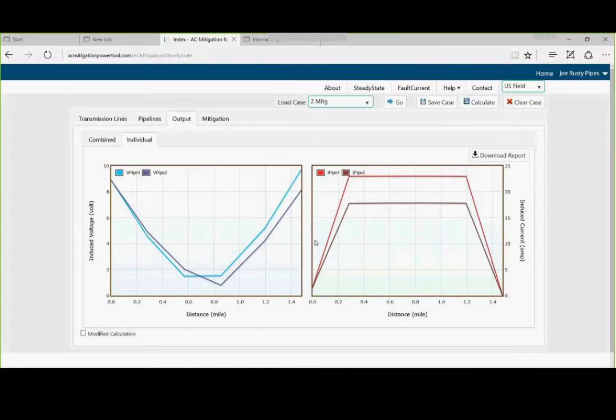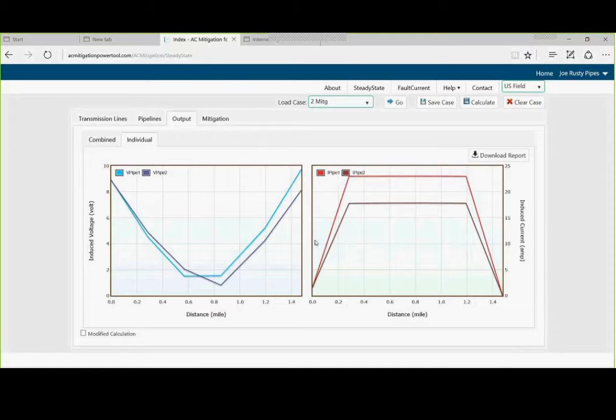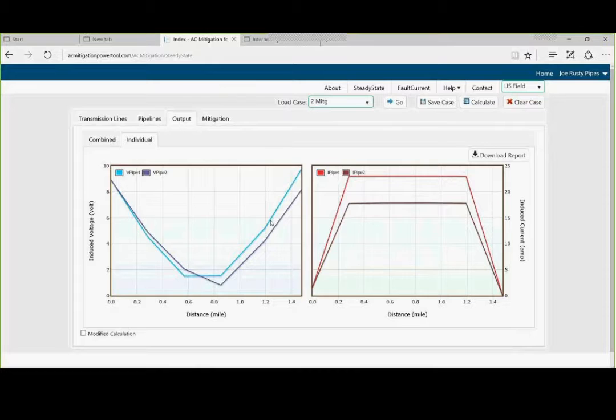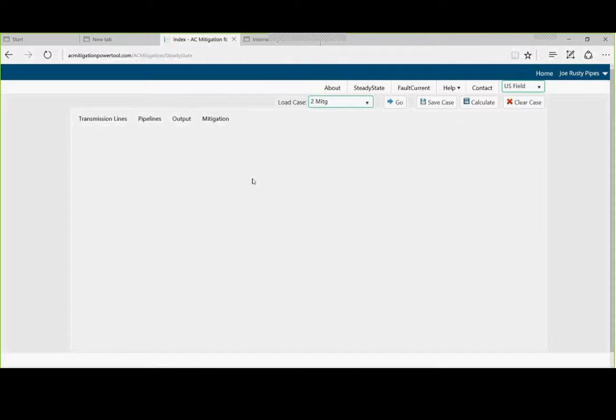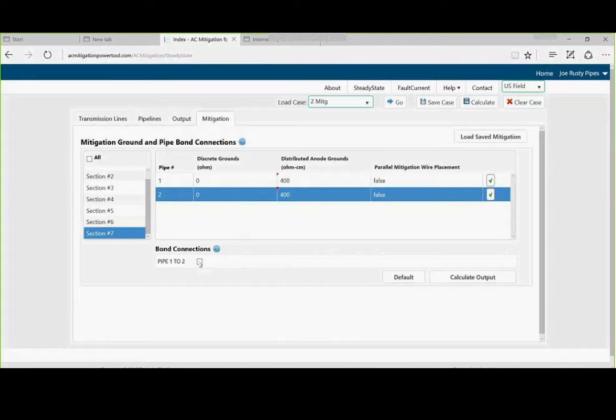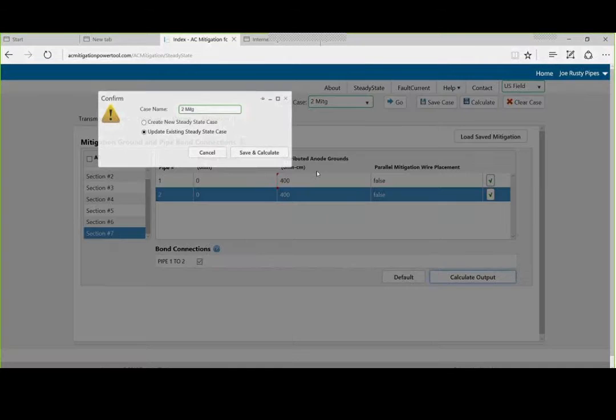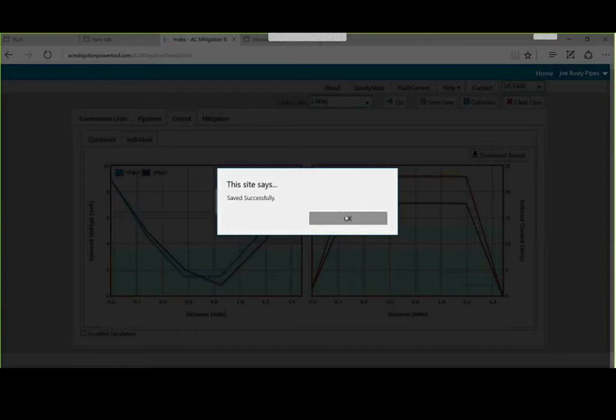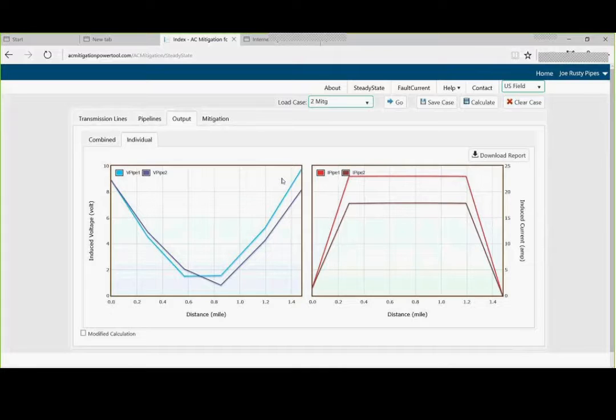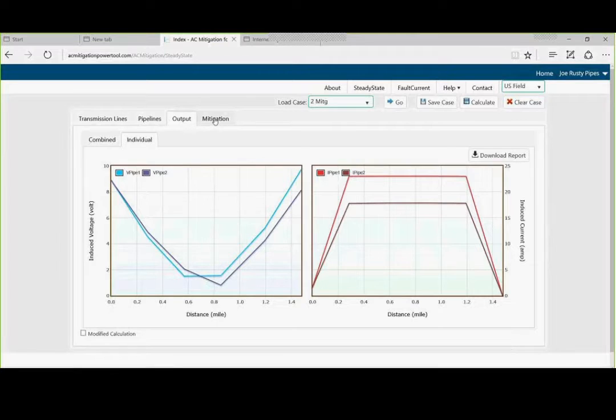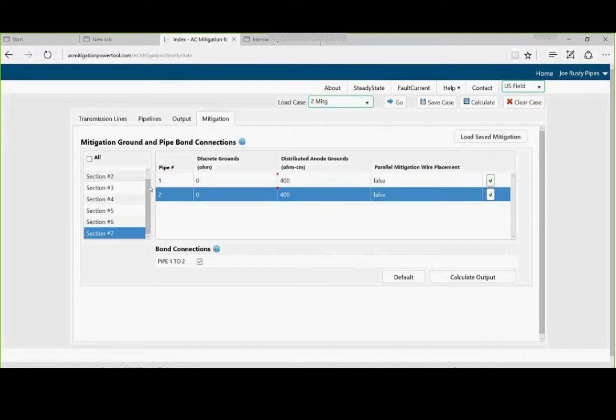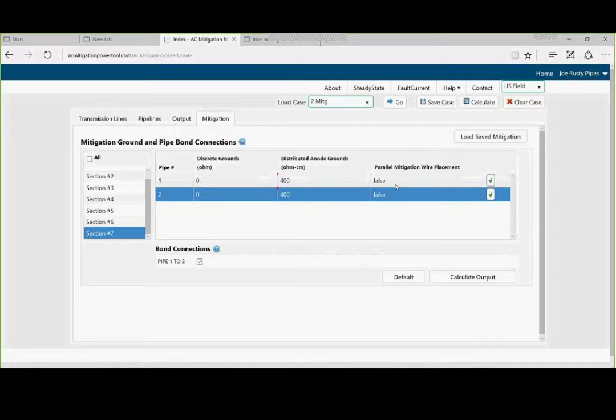And now, we can see that we have brought it down to about maybe nine volts on one end. Almost nine volts. And almost ten volts on the other end. What else can we do? Well, I don't think the guy bonded these cables. Let's see if that makes a difference. And let's calculate. Oh, it brought it down a little bit. What if we add it? Let's go back to the mitigation strategy.